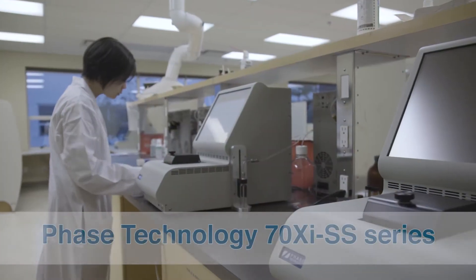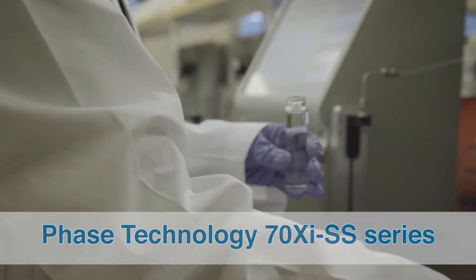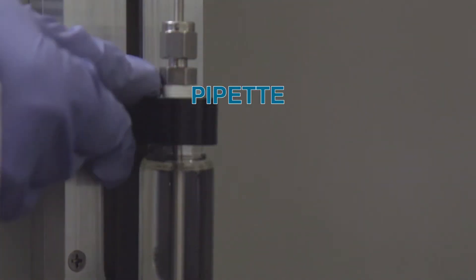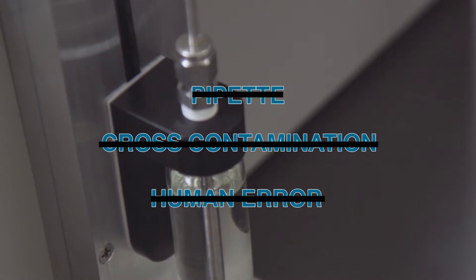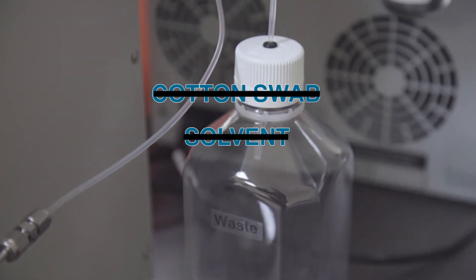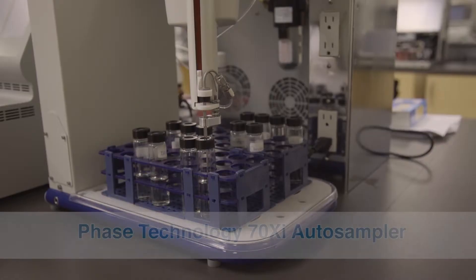The 70XI single-shot series laboratory analyzers feature an automatic sample input using a side-mounted glass vial injection system that loads the sample automatically. No more pipette, no more cross-contamination, no more human errors. The 70XI-SS is self-cleaning and therefore requires no cotton swab and no solvent. Its automatic flush cycle rinses and disposes of the remaining sample.